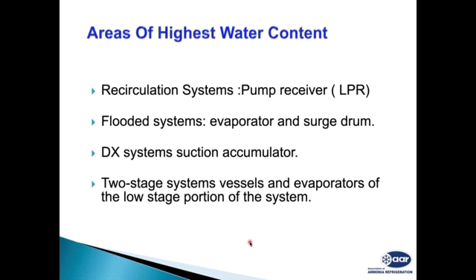These are all the effects of the water in the system. Where water accumulates: as we have seen, air accumulates in the high pressure side of the system, whereas water occurs on the low pressure side. So it can occur in the low pressure receiver system. If we have a high stage booster system, it will always occur in the booster system. In flooded systems, it will find water in the evaporators and surge drum. In DX systems, it will be in the suction accumulators.